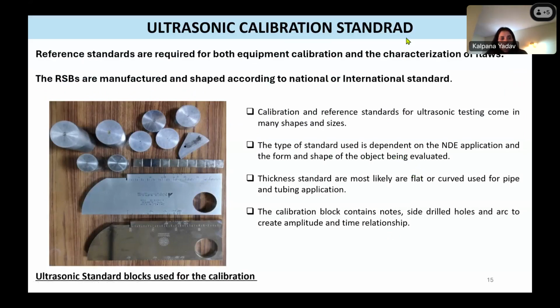If you are going to do pipe inspection or something similar, you are going to use a flat bottom hole. If you are doing thickness measurement, the standards are most likely flat or curved, used for pipe and tubing applications. The calibration block contains notches, side drilled holes, and arcs to create an amplitude and time relationship.